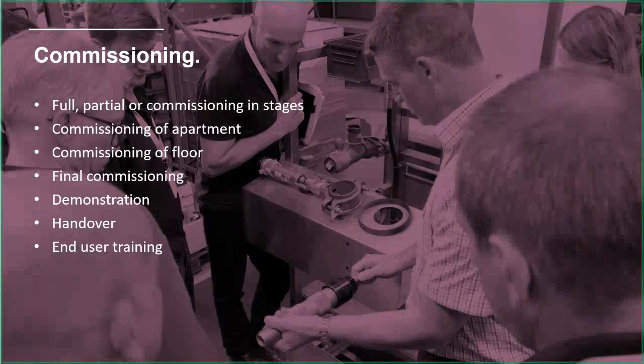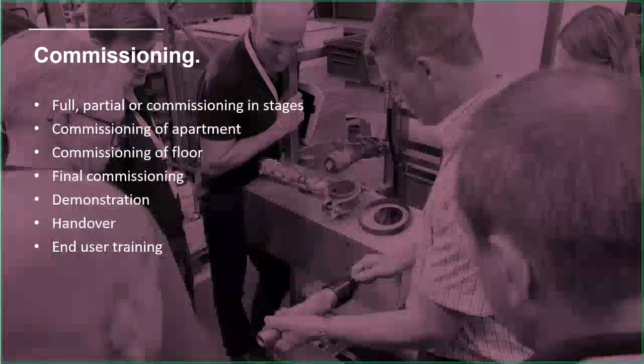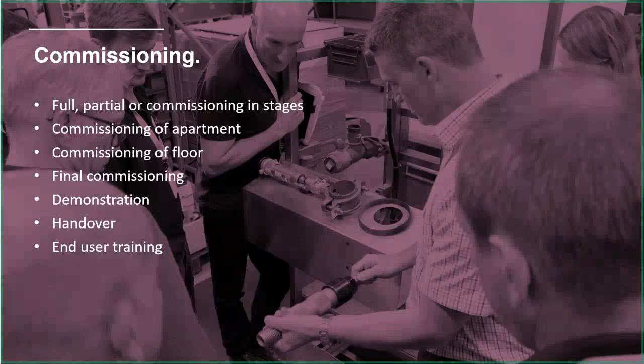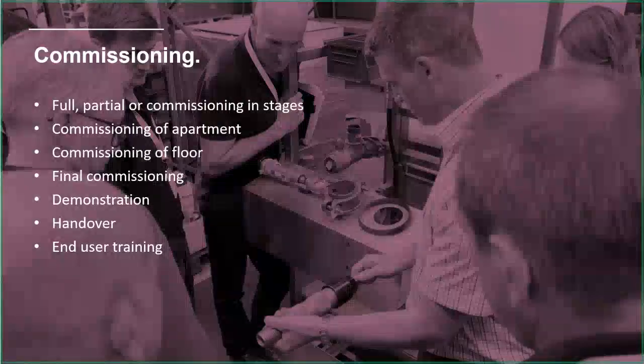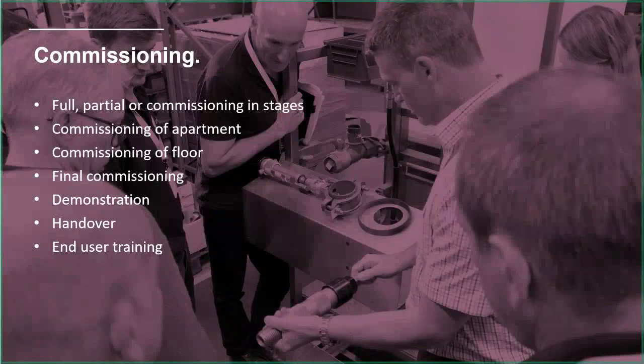At the other end of the scale, you might have a large shopping centre, or a complex high-rise building, in which case you're probably going to be doing commissioning in stages. You might even have what's called a base build, where one sprinkler contractor is going to come in, install the tank, the fire pumps, the distribution pipe work, the main pipe work, and then branching off to each floor level or to each shop unit, they would put an isolation valve, maybe the flow switch, or maybe a zone check, but say maybe just the isolation valve, and then cap it off, and that would be their work done.